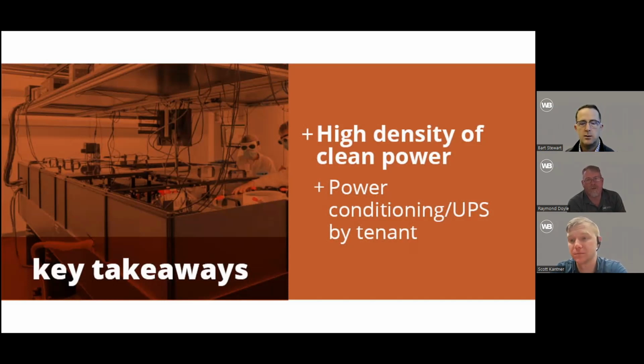One thing I'll add on high density power: we talk about clean power, but high density power is also very important. A typical R&D lab building would have somewhere between 8 and 12 watts a square foot of power available to the tenant in the lab. When we get into things like quantum computing, you're looking at anywhere from 30 to 50 watts a square foot inside the lab. So the amount of power needed to do this science is much higher than a typical R&D building, and we need to make sure that when siting a building or a space inside a building, you're taking that into account. A key takeaway is make sure you've looked into that and verified it.